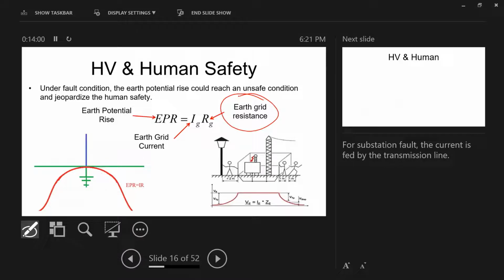And depending on the resistance of your system, your voltage will be determined. Is it high voltage, low voltage? When you inject 10 ampere into 1 ohm, it will give you 10 volt. If you inject 10 ampere into 100 ohm, it will give you 1000 volt. 1000 volt, you know, your body might not withstand it.